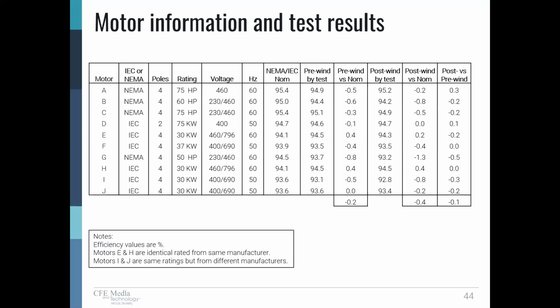Summary results: here are the 10 motors alphabetically labeled. These were randomly labeled from A to J. So we have these test results, and I'm not going to go through them, just display them. But if we look at the far right column, the post versus pre-winding, you see the top one happened to be the plus 0.3 gain, and we've got 2 that had a gain and 2 that had no change at all, 0, and then the remainder had some slight loss. So the net change was 0.1%.